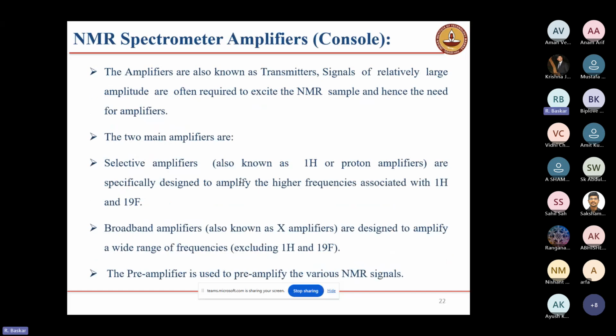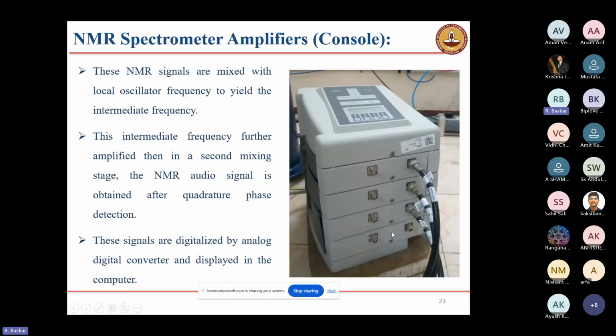Next one is the amplifiers. The amplifiers, also known as transmitters, provide signals of relatively large amplitude required to excite the NMR sample, hence the need for an amplifier. The two main amplifiers are, one, the selective amplifier. This is for proton. It gives only the proton frequency, or at maximum fluorine also. These two frequencies it will generate. Another one is the X nucleus broadband amplifier. It will cover all the remaining nuclei. The preamplifier is used to amplify the signals we have received, and it will send them to the computer.